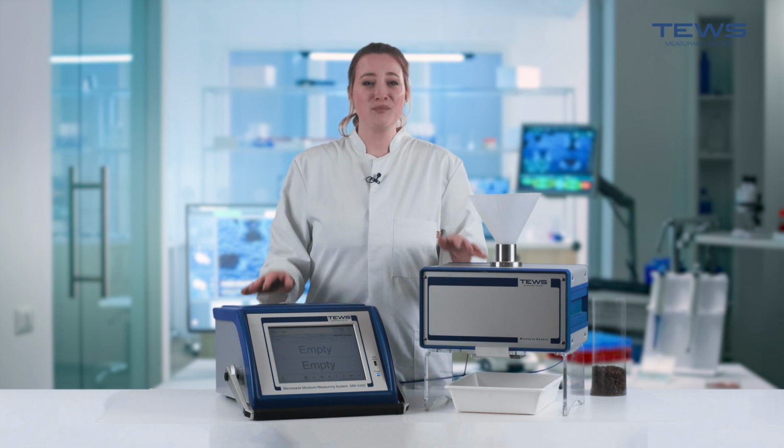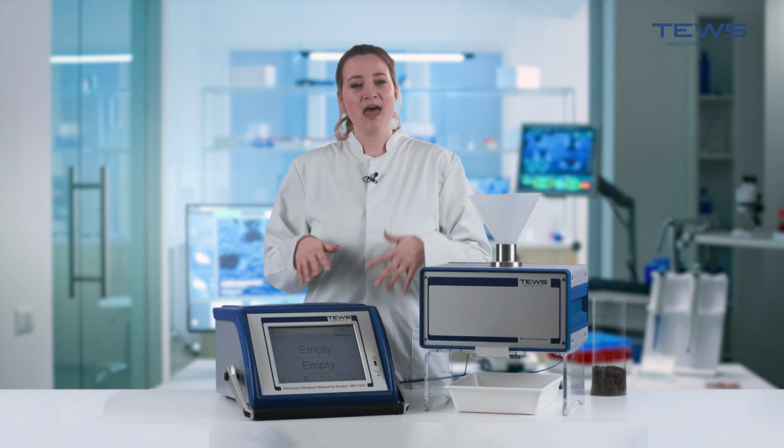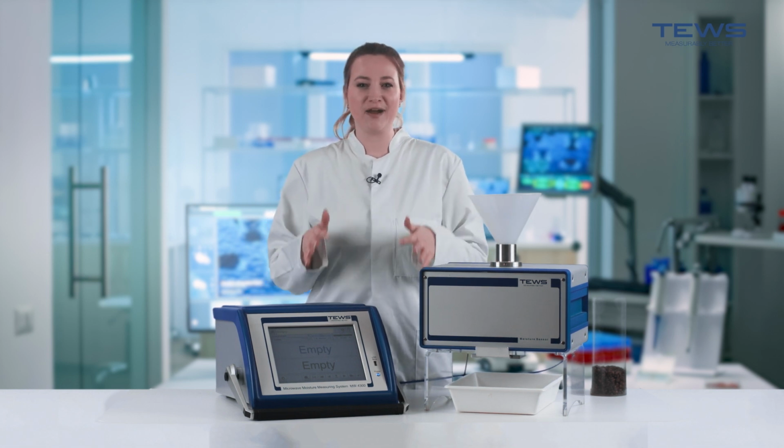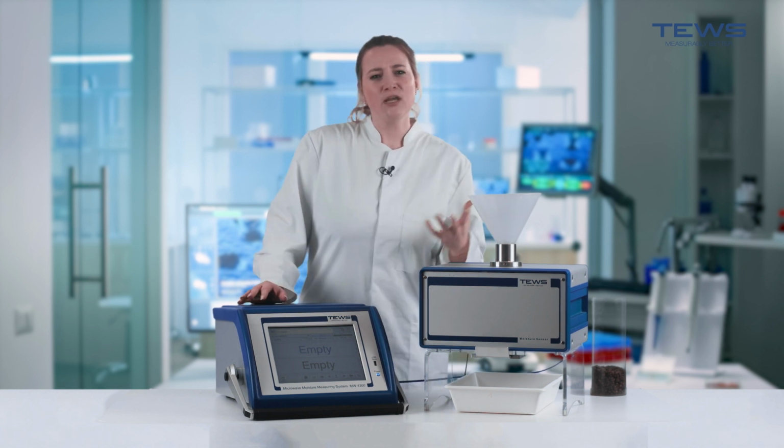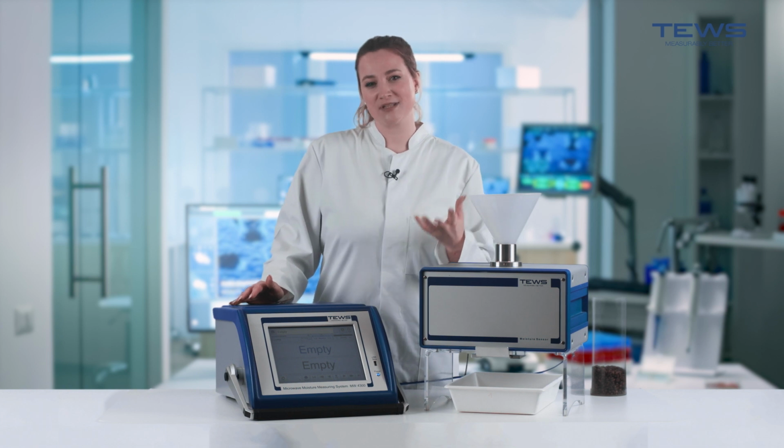On top of that, they don't compensate density, meaning the amount of product on the sensor correlates with the amount of moisture the sensor detects. This can damage your results by making the moisture measurement higher than it actually is. We, on the other hand, mostly have such a high frequency that no other ingredients affect our final moisture results. On top of that, we measure density, meaning we compensate the final moisture results.